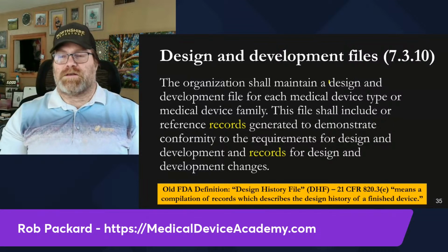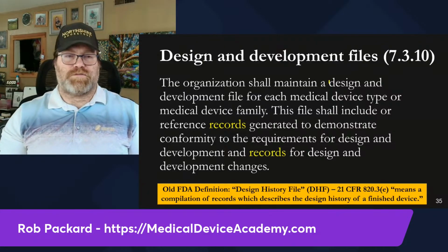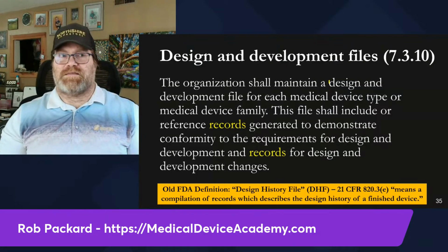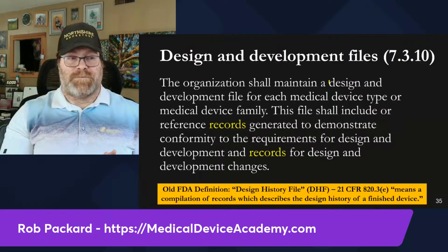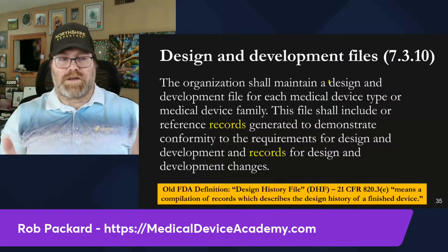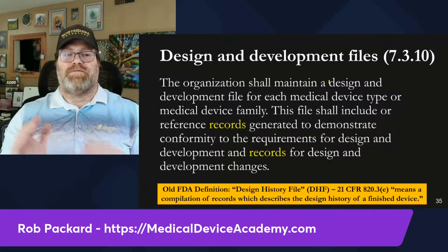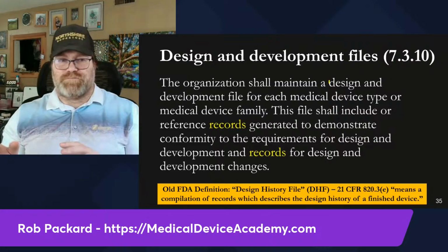They were asked, are you going to come up with a new term, new definition? No, we're not. What? Yeah, ISO 13485 already has it. It's design and development files, clause 7.3.10. That's good. We're good. That's what we need. So it's the same intent. It's just everything, all the compilation of records that was in the history of your device.